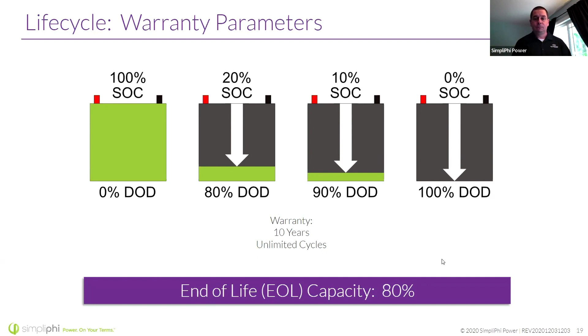Now, and I should have said at the top here, the numbers up top are state of charge. So 100% state of charge is 0% depth of discharge. It's a very common terminology in the industry, but we do allow you to cycle to 100% depth of discharge if you want to. Now, we recommend 80% depth of discharge because we know from experience, from batteries that are still out there in the field, that if you're very kind to your battery and not going to 100% very often, your battery will outlive 10 years. And I believe we have a slide on that coming up here.